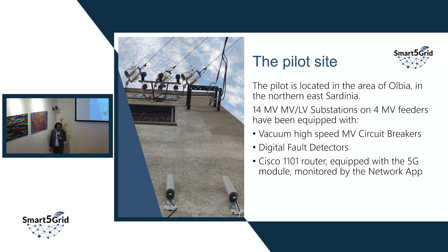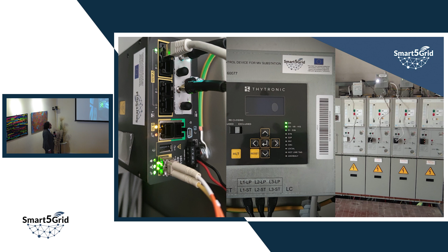And these are the pilot sites. In each secondary substation, we implemented high-speed circuit breakers, a series of digital fault detectors, and a router able to utilize 5G with a dual APN. These are the three main devices implemented on field.